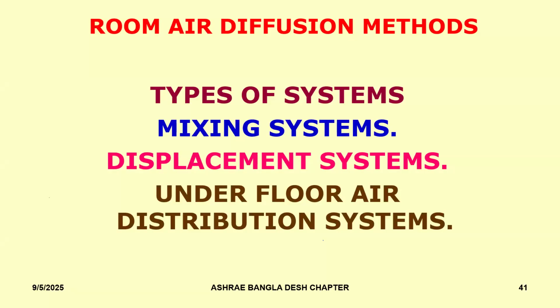So now, having seen what worries us in terms of air quality, let's try to see what are the different types of air distribution systems that are available to us that will help us to make sure that we can provide a good indoor environment for people. So the three types of systems that are most commonly used: one is the mixing air system. Mixing air system is the one that's most widely used. 90 to 95% of the spaces you walk into will have a mixing air system.